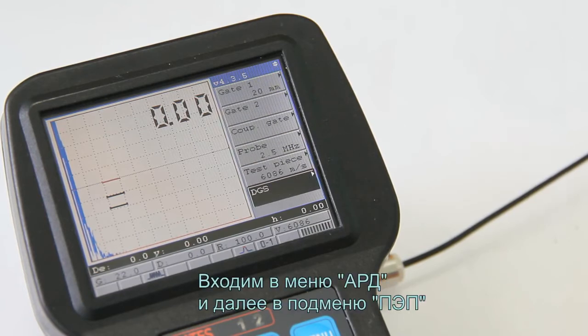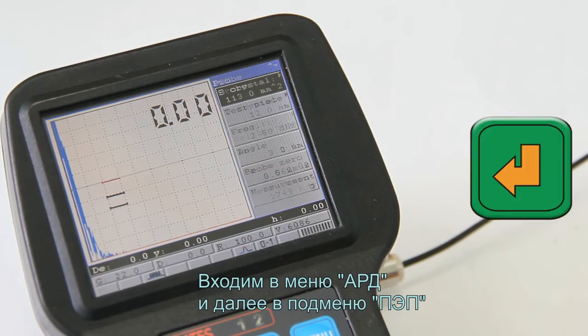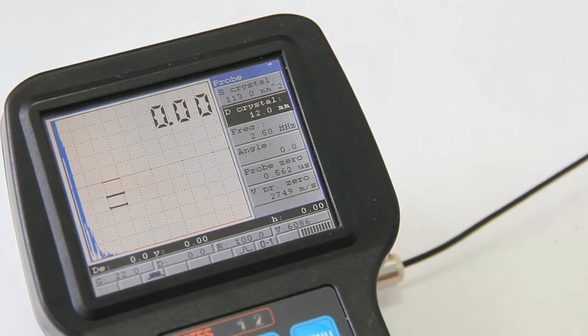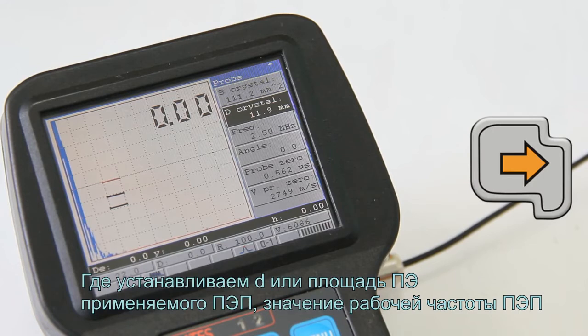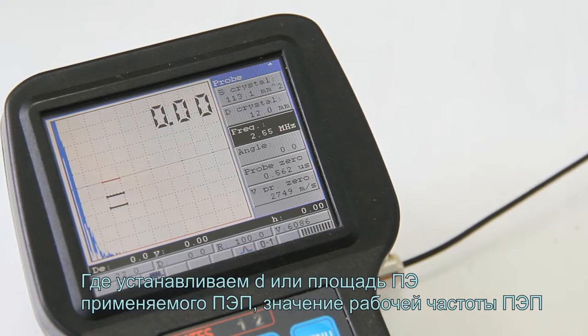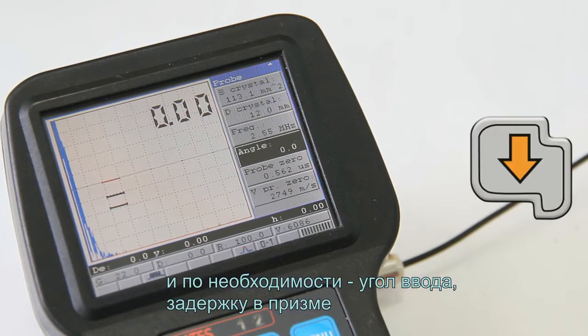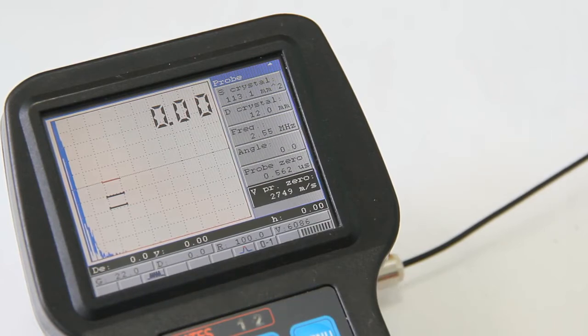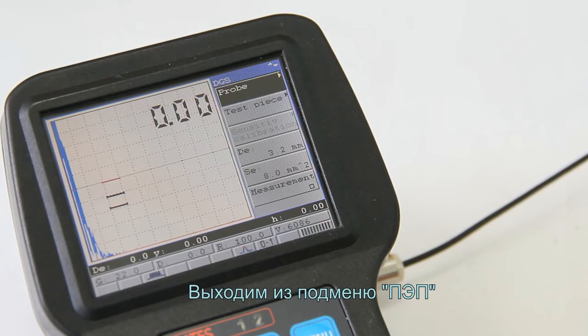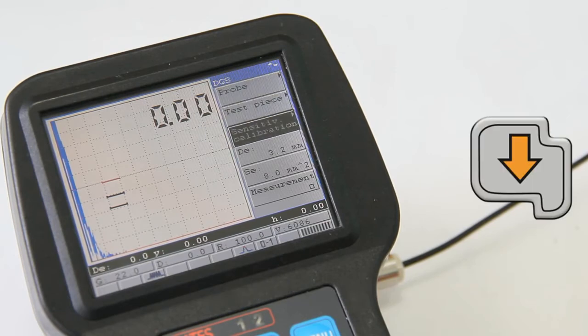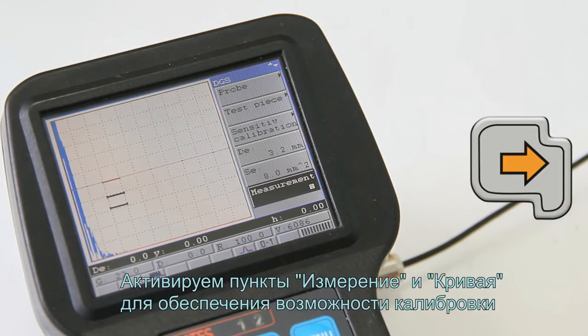Enter the DGS menu and then enter the probe submenu, where set up the D crystal or S crystal of a used probe, the true value of a probe operating frequency, and if required, angle and probe 0. Exit the probe submenu. Activate measurement and curve items to ensure the calibration option.